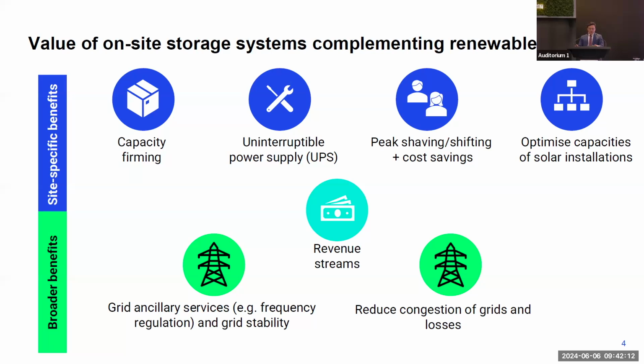Beyond site-specific benefits, on-site ESS can also provide value to the grid, including ancillary services such as black start, frequency regulation, and voltage control. ESS is a good source because it can inject electricity extremely fast and with higher accuracy than conventional generators to provide system reliability services. It can also reduce grid congestion by storing electricity produced when the grid is too congested. Overall, on-site ESS can support the decarbonization of the textile sector.